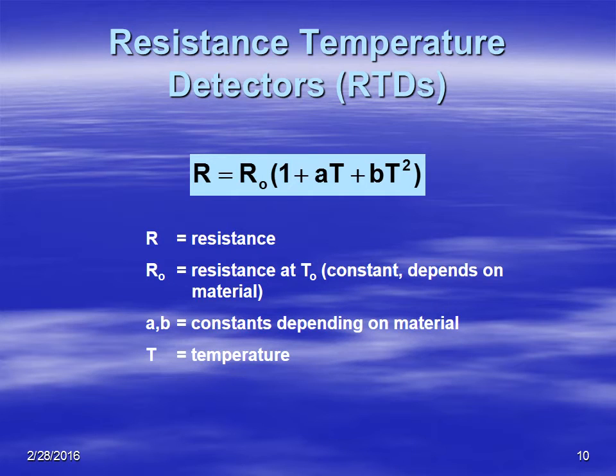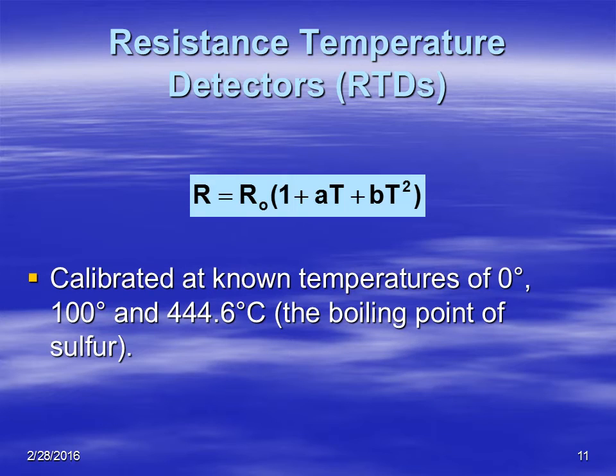Here is the calibration equation for a resistance temperature detector. An RTD shows that resistance is a function of temperature, and it's not linear — there is a squared term, so it is non-linear. R-naught is your base or constant resistance, and with temperature changes you get a change in resistance. RTDs are calibrated at known temperatures of zero, 100, and the boiling point of sulfur, which is 444.6 degrees Celsius.